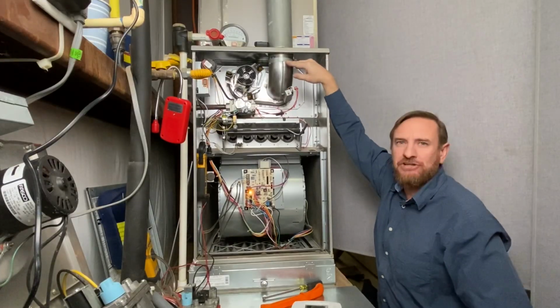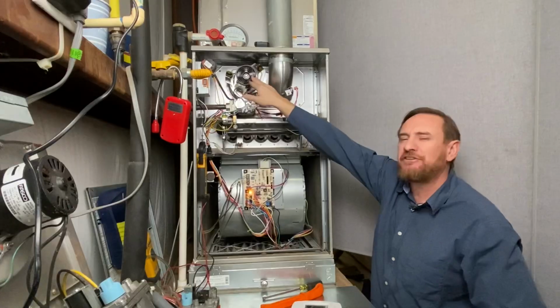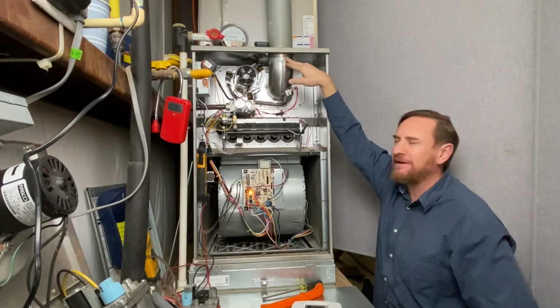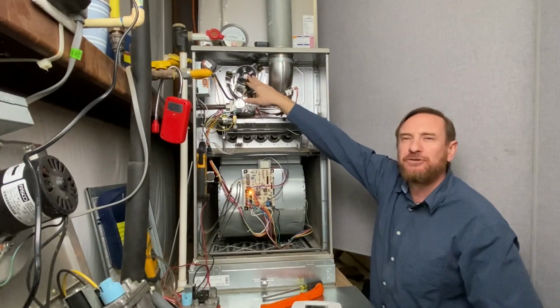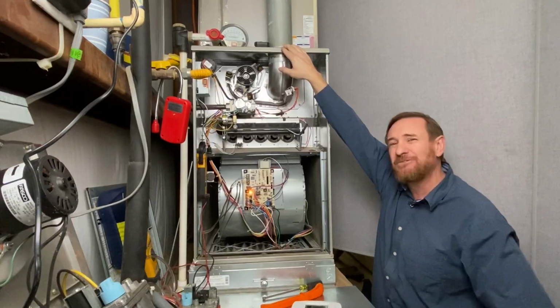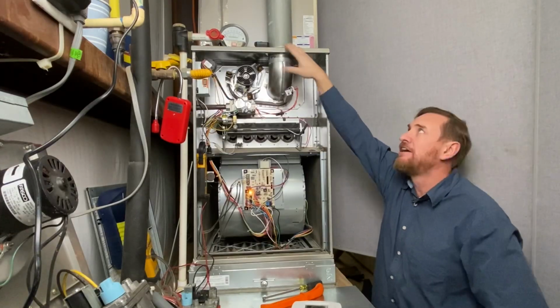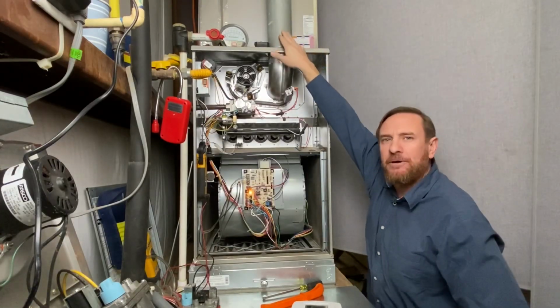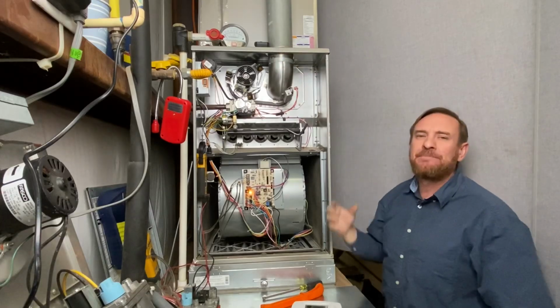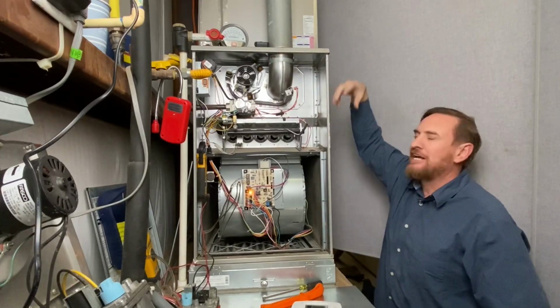It's not pressurized. A lot of people think because we have this fan motor, this is a pressurized pipe. And the truth is, this fan motor is too small to pressurize this pipe. It still relies on natural convection for it to heat up. We have double wall vent pipe right here. That inside pipe has to heat up so it can naturally draft out.